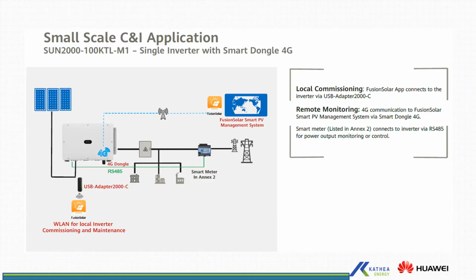And then the wiring setup of the system. Our inverters can be wired from single to multiple inverters. You can even have different inverters daisy chained together. So for a single inverter, in this case a 100 KTL, you can use a Smart Dongle 4G to connect to the FusionSolar app, or to the website, the PV management system, through your 4G internet.